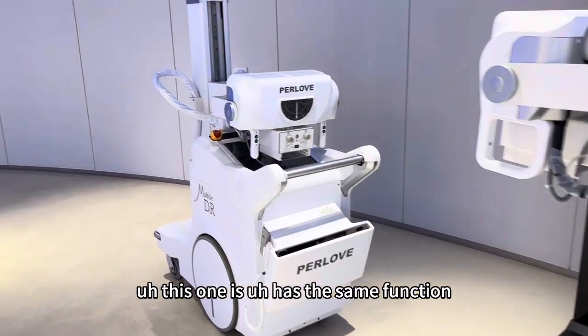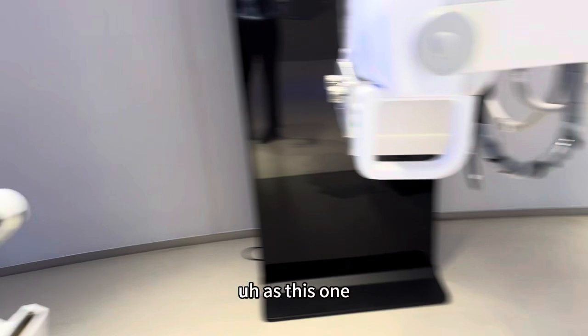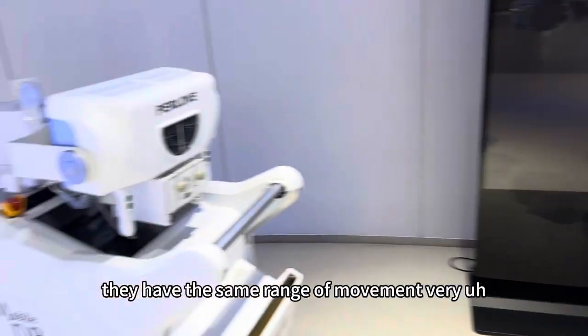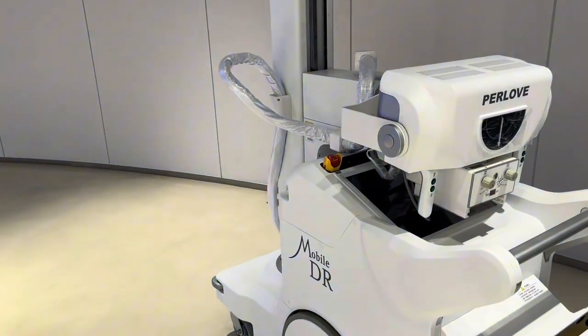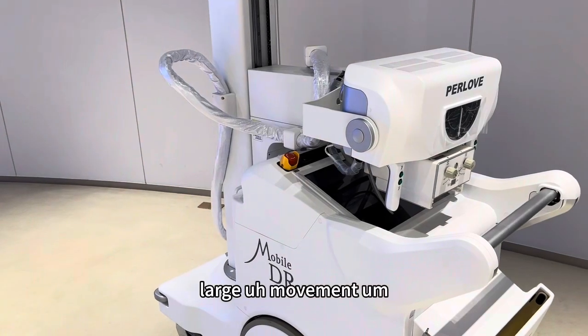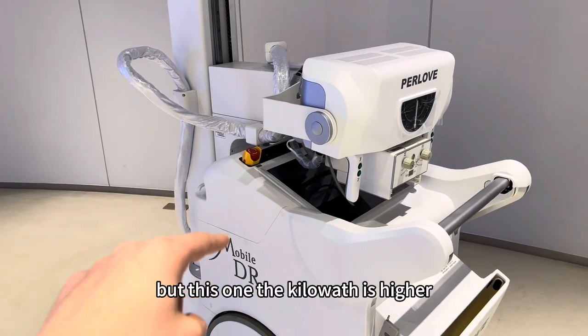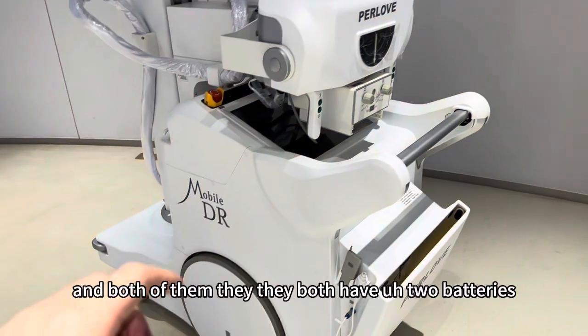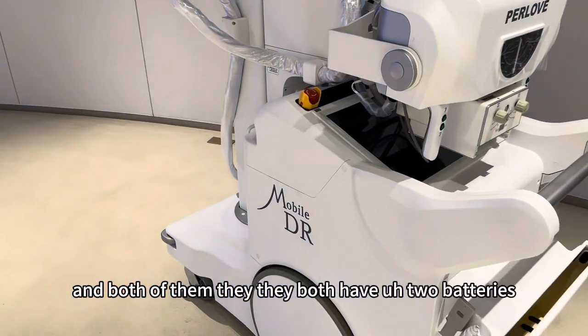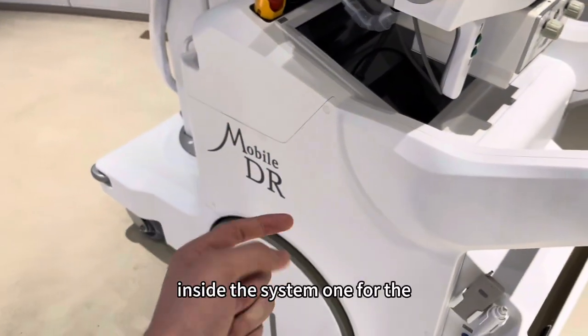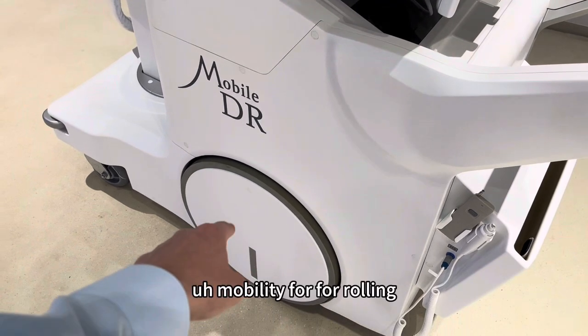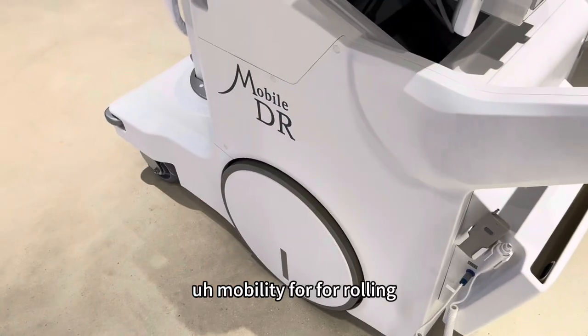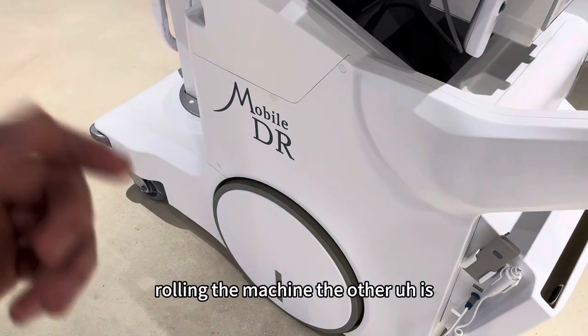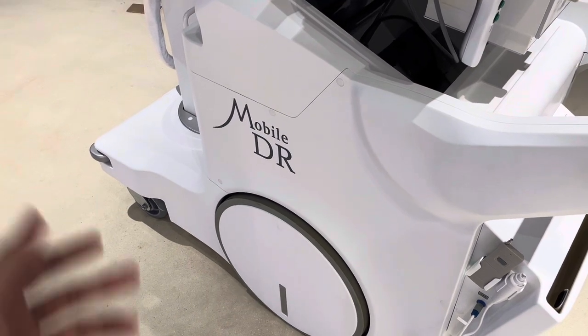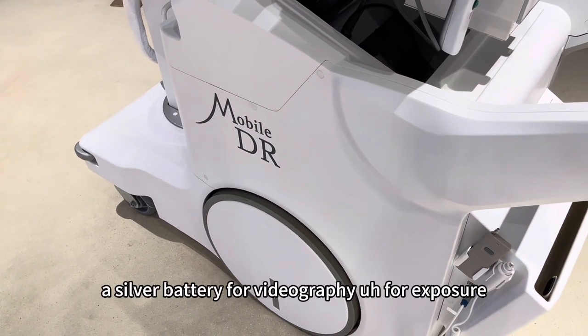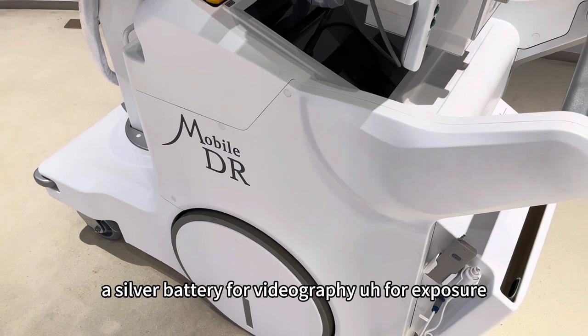This one has the same function as this one. They have the same range of movement, very large movement, but this one, the kilowatts is higher, and both of them have 2 batteries inside the system. One for the mobility, for rolling the machine. The other is a super battery for radiography, for exposure.